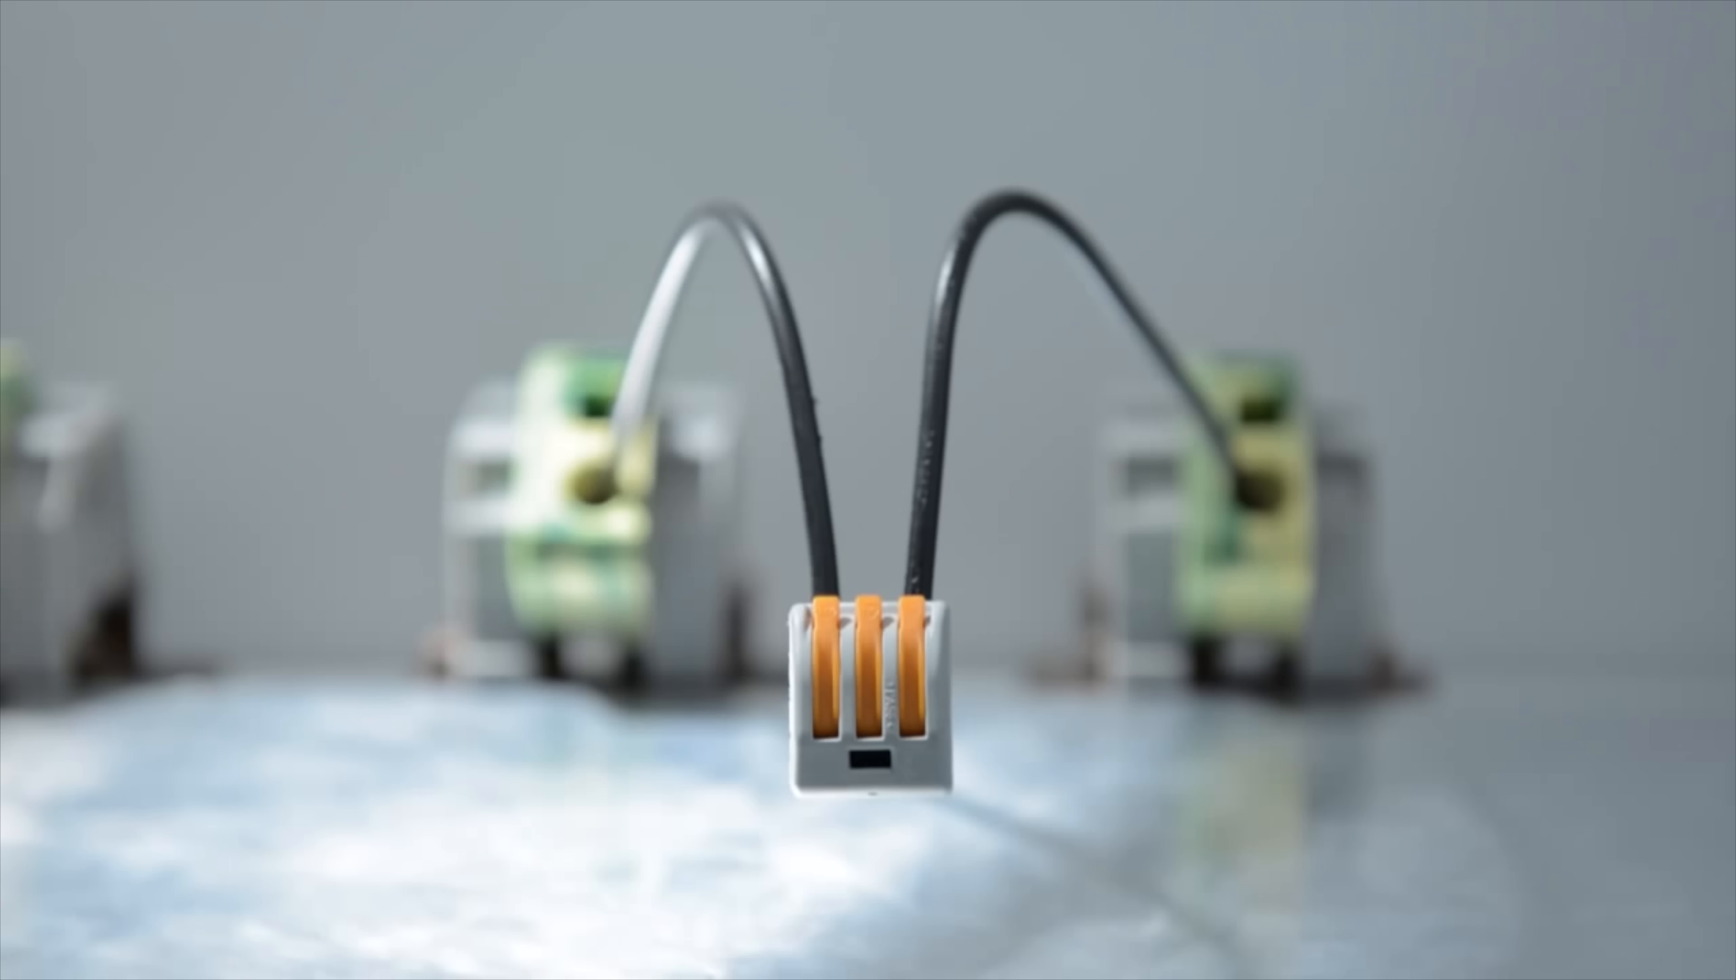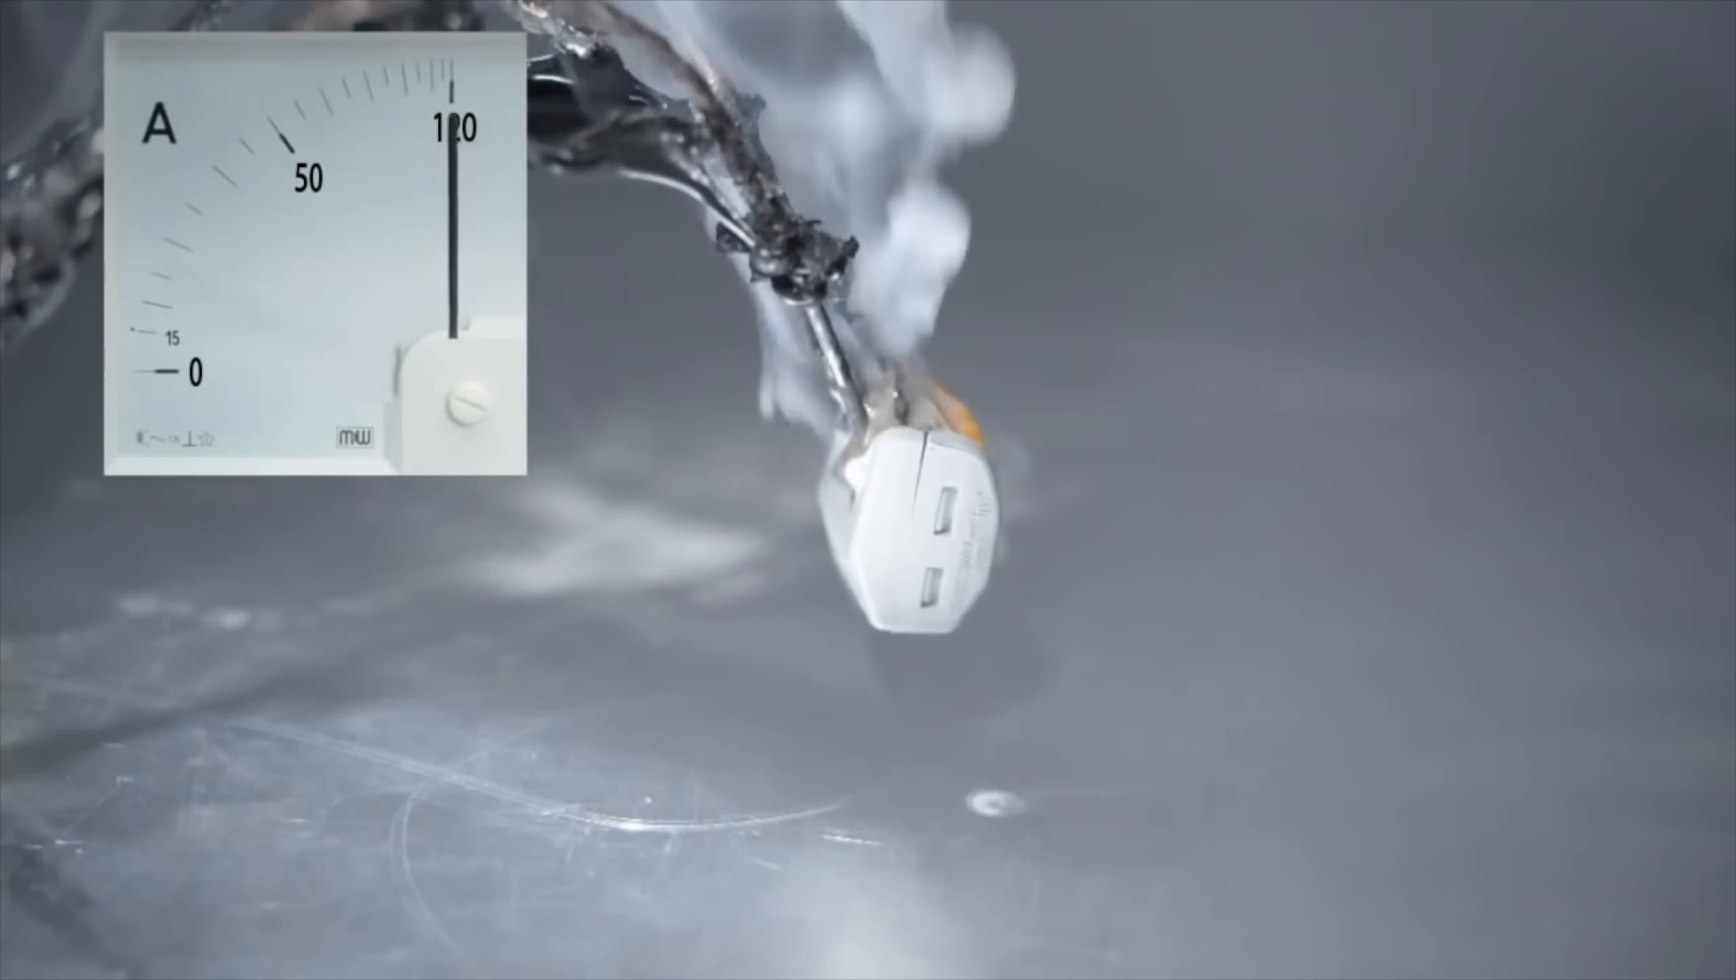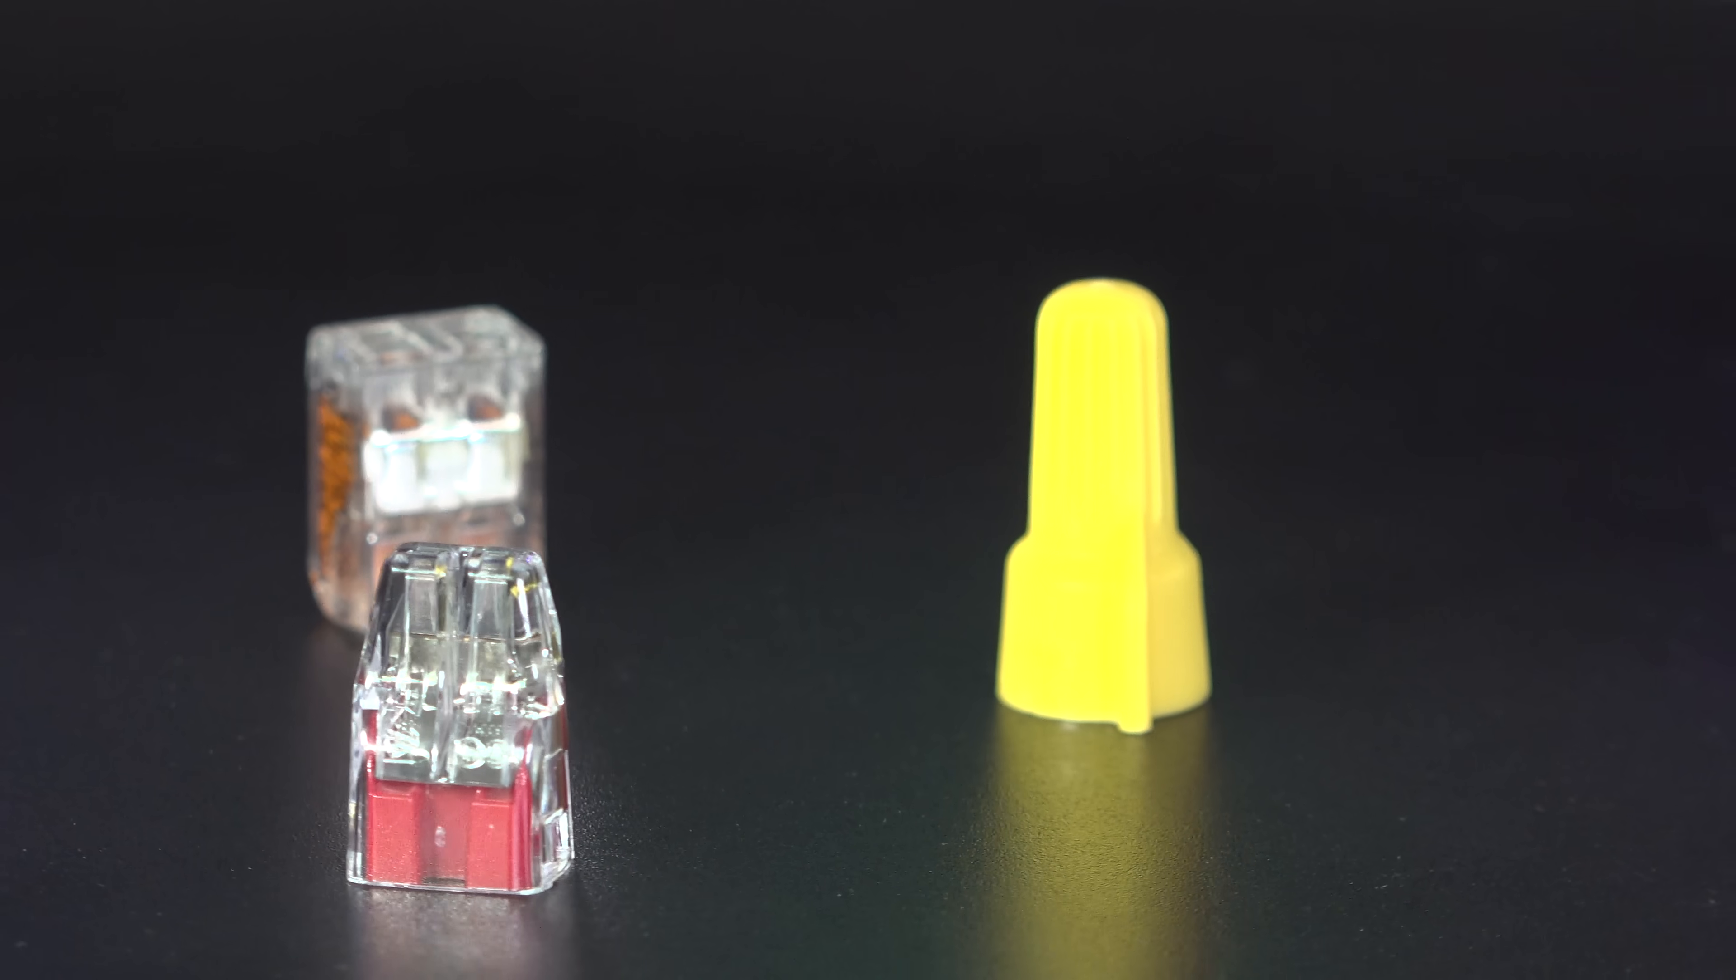After doing all these tests, the bottom line is that these connectors are really well engineered. It's amazing that these things could hold up under 60 amps of power, but either way, whichever one you choose, just pick the one that works for you and then you're the most comfortable with. But I wouldn't think twice if you decide to use one of these Wagos. They're definitely a capable connector and the slight temperature difference I saw between the wire nut and the Wego at 60 amps wasn't enough to make me think they were superior in any kind of connectivity sort of way. Either way, I hope you found this video helpful and gave you some good information. If you liked it, please give me a thumbs up and subscribe to my channel for more videos coming up.